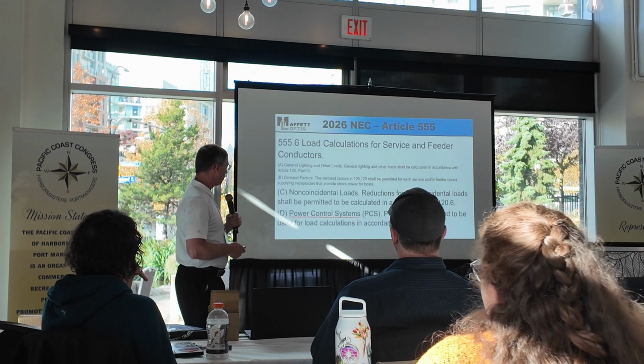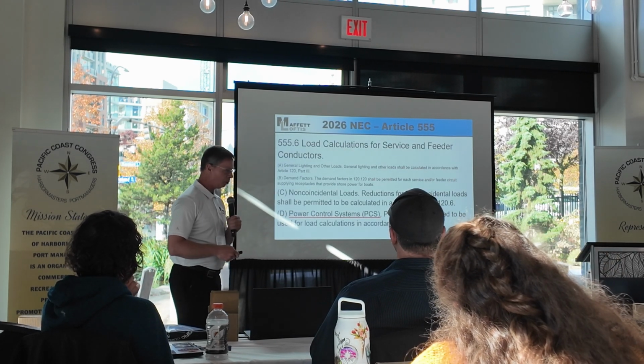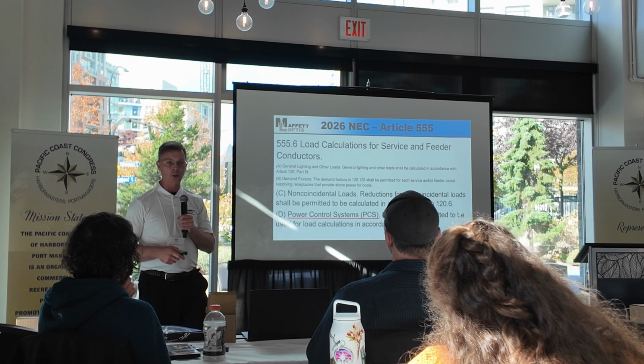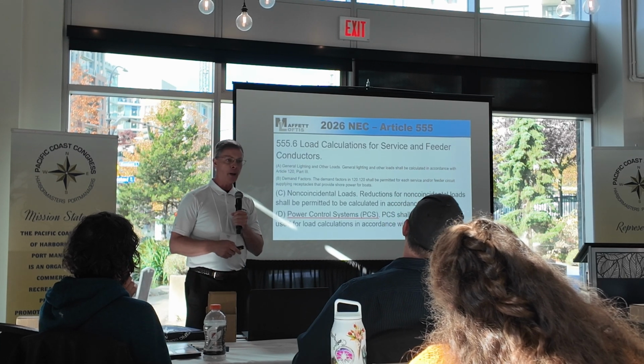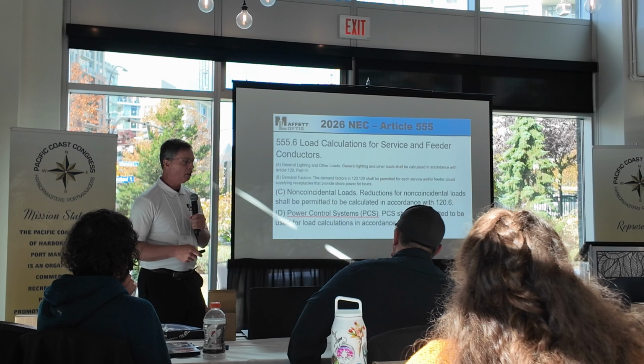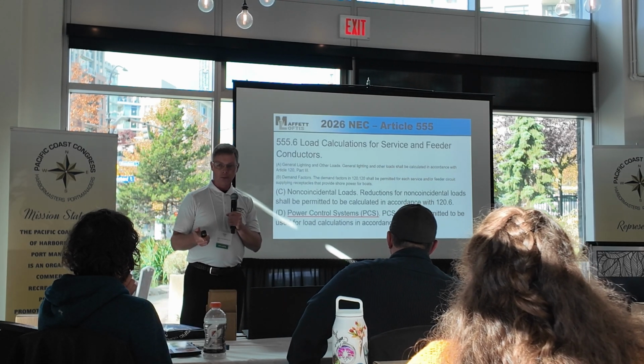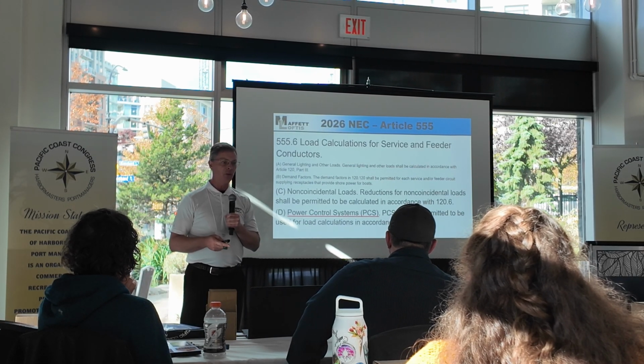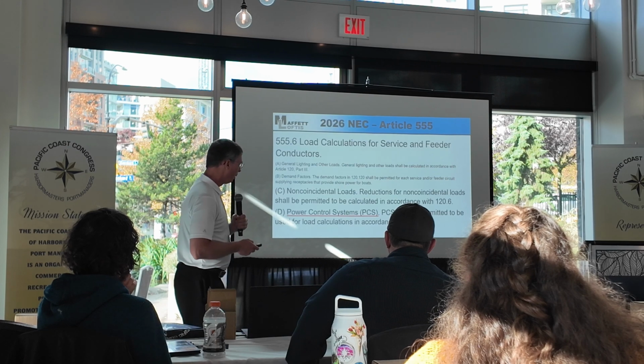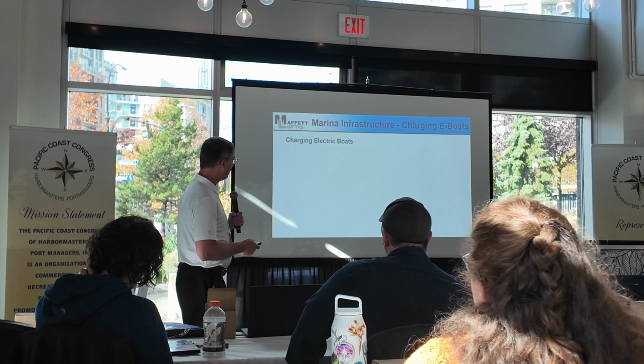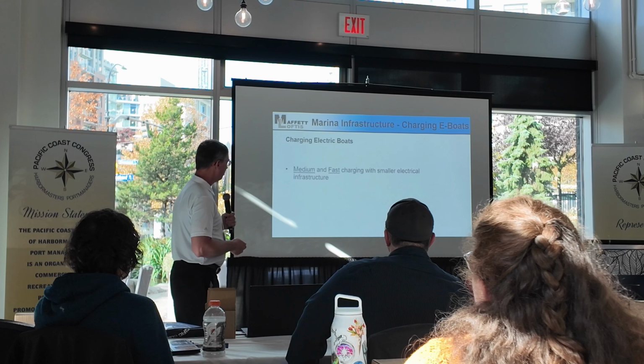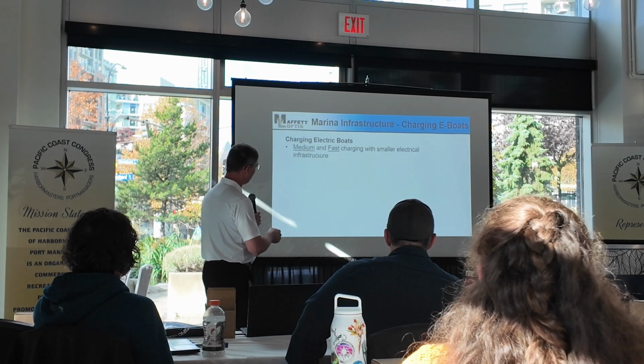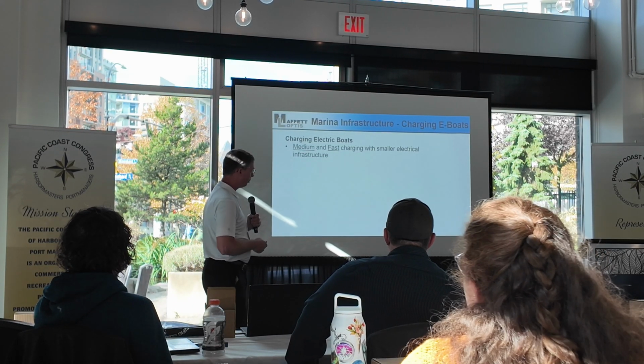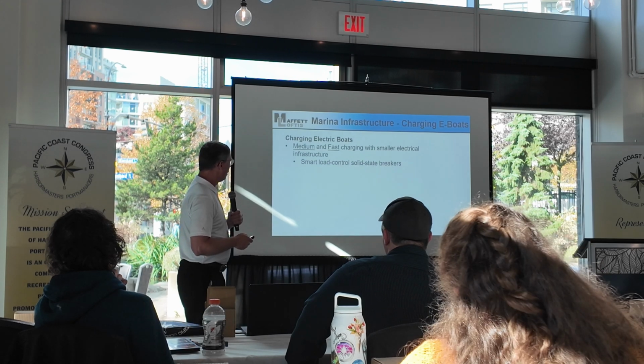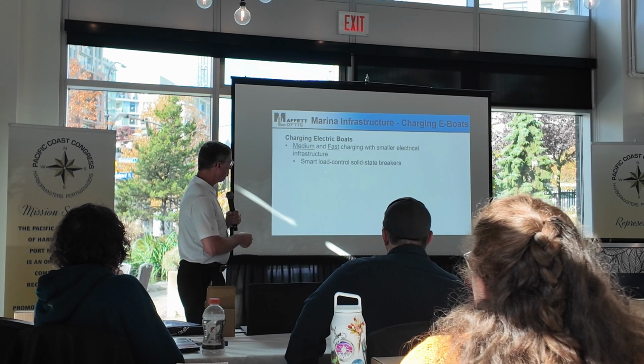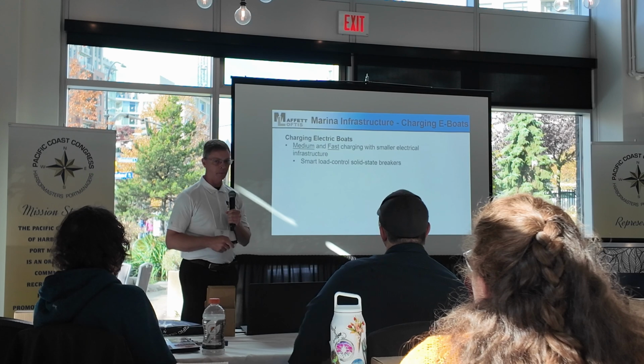And then the next one is power control systems, and you may not be very familiar with that because that's some new technology that's coming around for power control. And within the electric vessel realm, which I've designed quite a few systems for, those shall be permitted. And here under electric boat charging, which I do a lot of, that'd be level 2, level 3 if you want to look at it that way. But there are smart load controllers and solid state breakers that are available now.